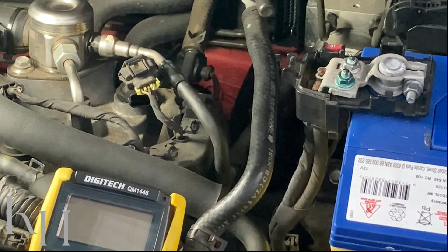The last wire was ground. You can check the ground as well by selecting resistance on the multimeter. The far right wire is ground. I'm going to put one end of my multimeter here and the other on a good ground. As you see, I'm getting continuity and low resistance, which means this wire is connected to ground and there's nothing wrong with that.